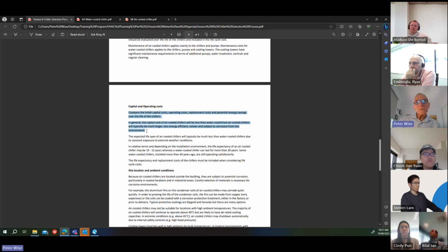Capital cost of air-cooled chillers is normally less than a water-cooled chiller of the same capacity. May not be, they might be very similar, but air-cooled chillers will typically be much larger, less efficient, noisier, and subject to corrosion from the environment. Expected lifespan of air-cooled chillers is typically much less than water-cooled chillers due to the constant exposure to external weather conditions.